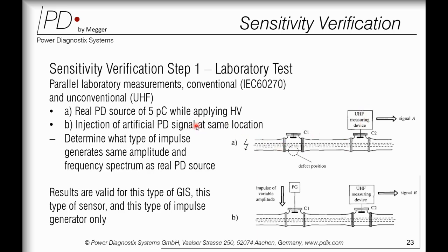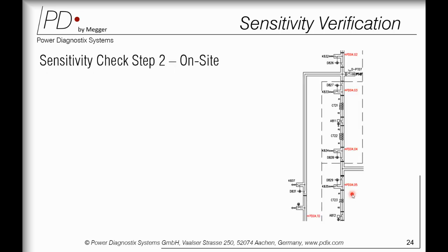Once again you de-energize your GIS and use a pulse injector. You inject the pulse and increase the pulse injector values, and you make sure you get the 30 dB microvolt value, similar to what you got with IEC 60270. Of course, a tolerance of plus or minus 20% is acceptable. Once you have done this activity, you make sure you have those values.